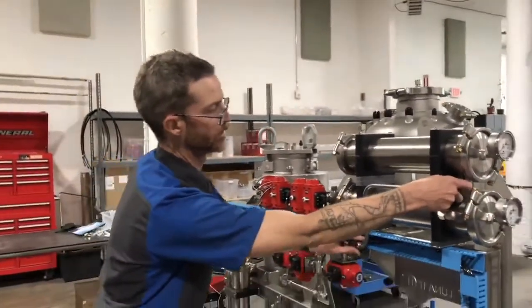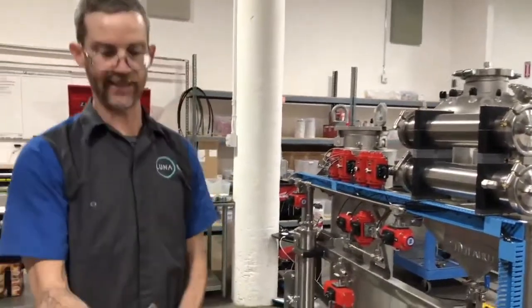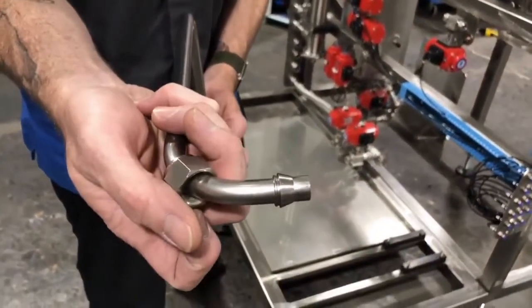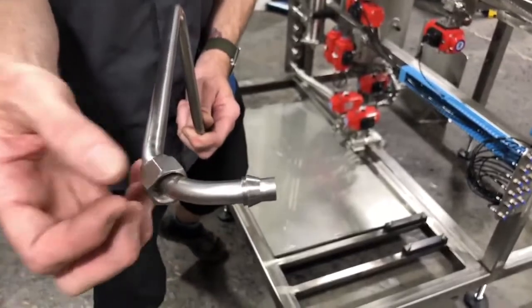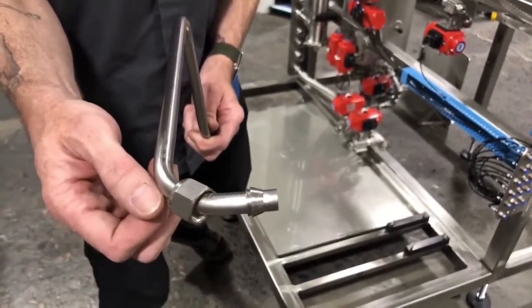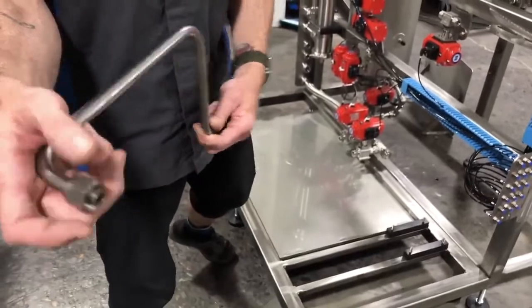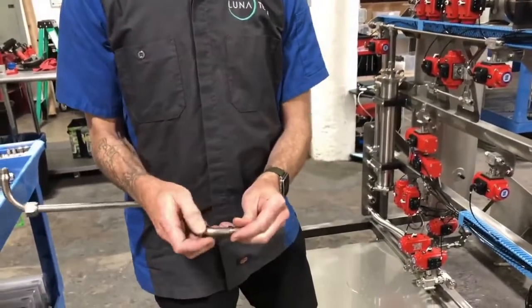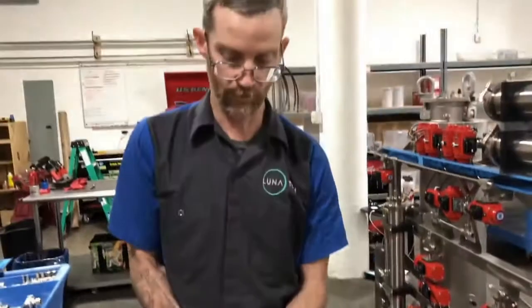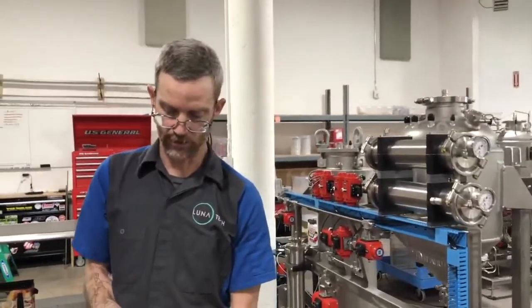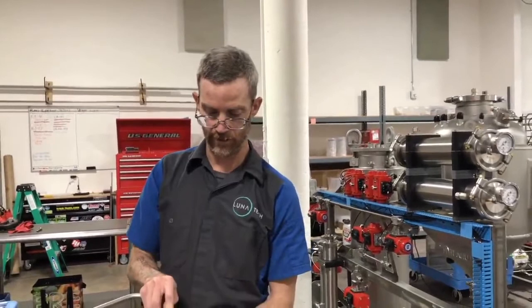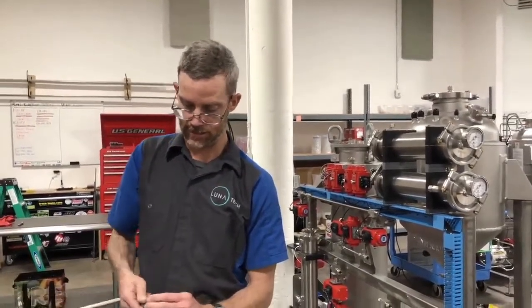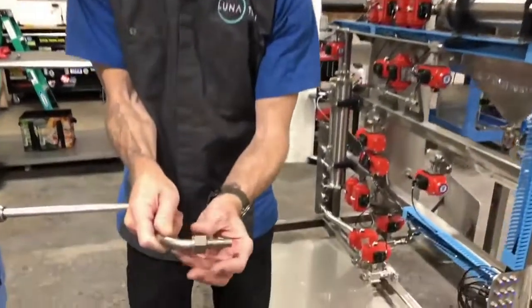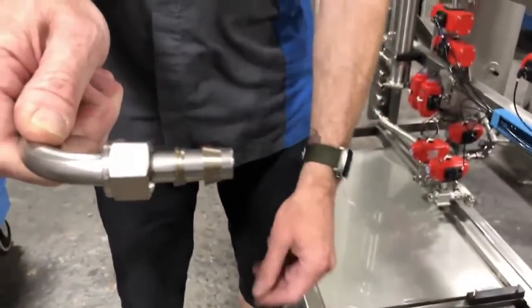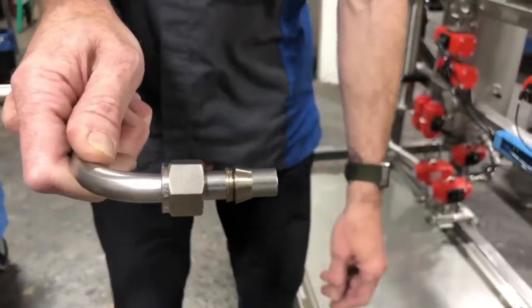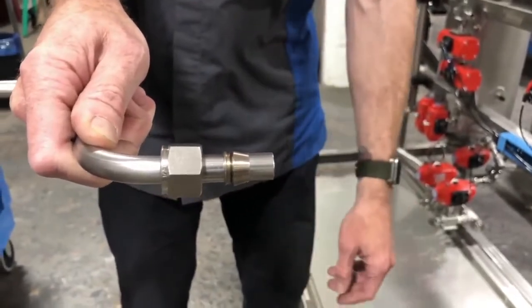You can take a look here, it's a very easy thing to fit in. These are compression fittings, Swagelok, Hamlet - there's a few other brands that use a very similar system, but a very secure way to prevent leaks in process lines. We've got a nut, a nut and 2 ferrules. These ferrules do have to be oriented correctly in order to provide the best fit with no leakage.